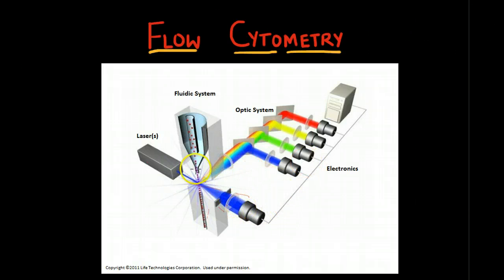Each suspended cell that passes through the beam scatters the ray, and the fluorescent chemicals that are found in the particle or attached to the cell may emit light at a longer wavelength than the light source. This combination of scattered and fluorescent light is picked up by these detectors.